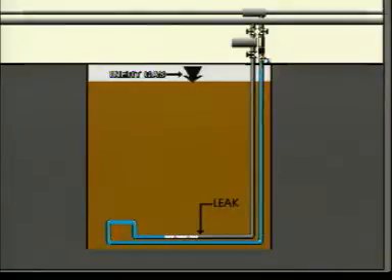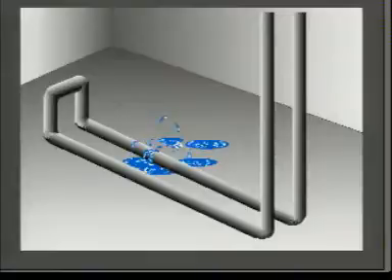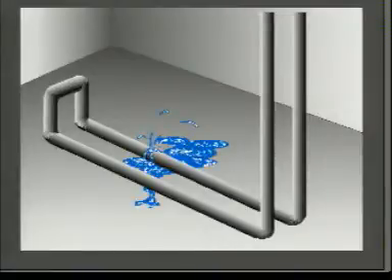If there is a leak in a fully loaded tank and the return drain cock is opened, water, propelled by the inert gas pressure, will start to flow to deck. If there is a leak on a coil in an empty tank, the water will leak into the tank. An empty coil means trouble.